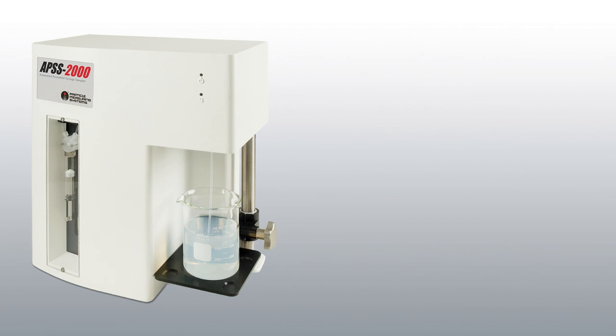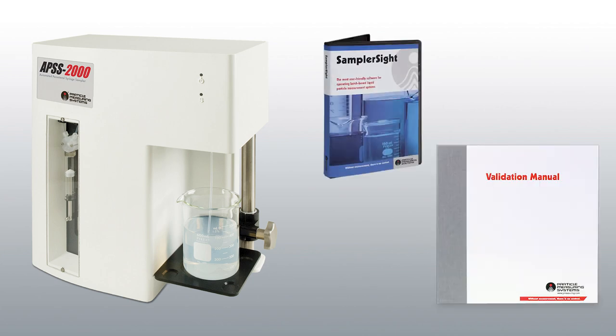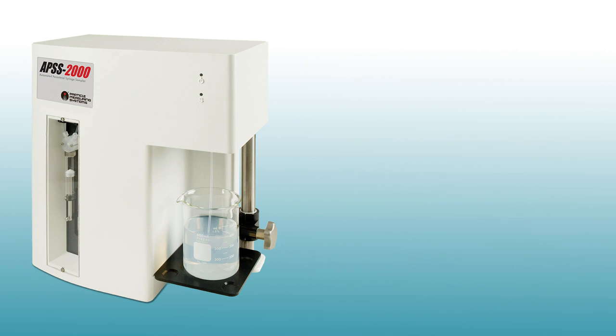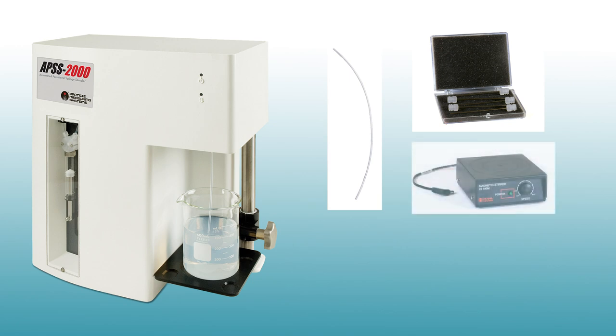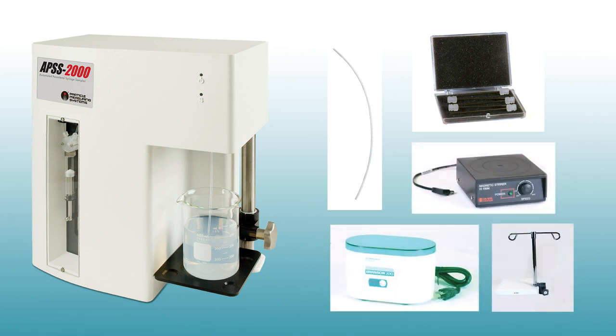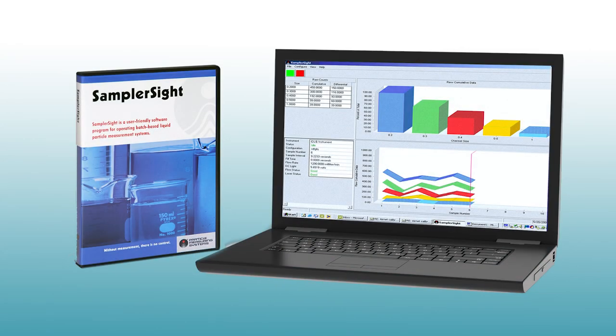So when you purchase an APSS-2000, it includes a particle counter, syringe sampler, software, and a validation manual. It comes with flexible sampling options. You can have tubing, you can have needles, you can use a magnetic stirrer, an ultrasonic bath, or an IV bag holder. And the software is simple yet functional. It's graphical, tabular. You can generate reports either manually or automatic, and the entire system is 21 CFR Part 11 compliant. And then you have a calibration wizard to ensure that your instrument is always in calibration.